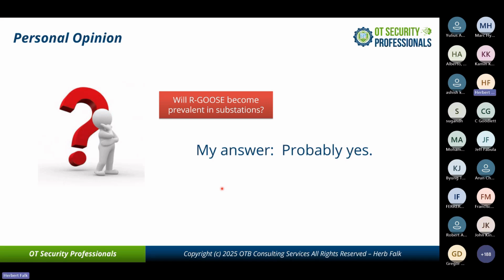I've been asked, will R-GOOSE become prevalent in substations, basically replacing layer 2 GOOSE? My answer is probably yes. There are several use cases for this, but right now the ecosystem doesn't allow that to happen. The use cases are, if you're publishing an R-GOOSE to go out over a wide area network, and that information needs to be consumed in the substation on the local area network, why wouldn't you just consume it on the local area network? Eventually, IP management of switches is going to become easier with IP routability, even if you don't allow it to go out of substations or manufacturing facilities. And that's my personal opinion.